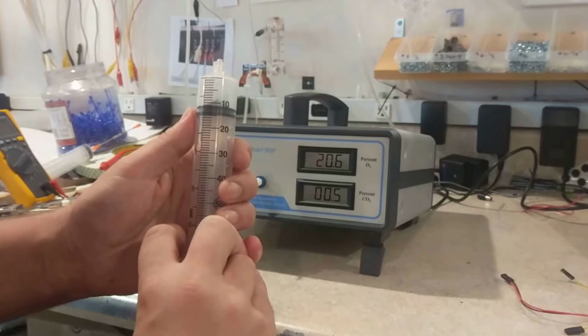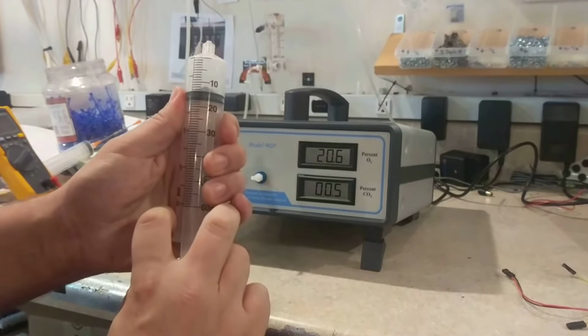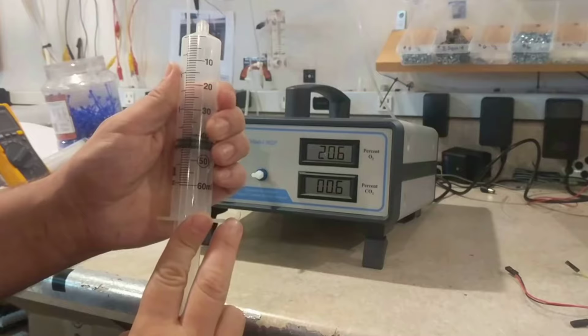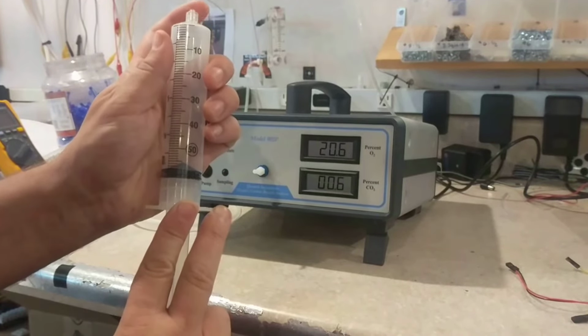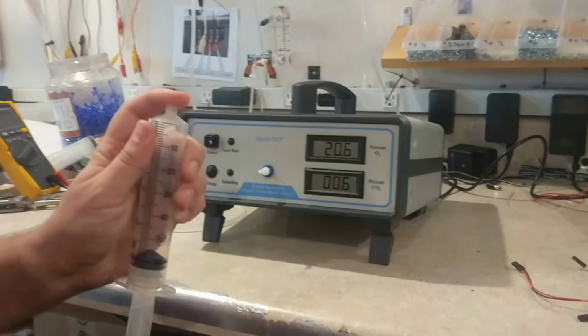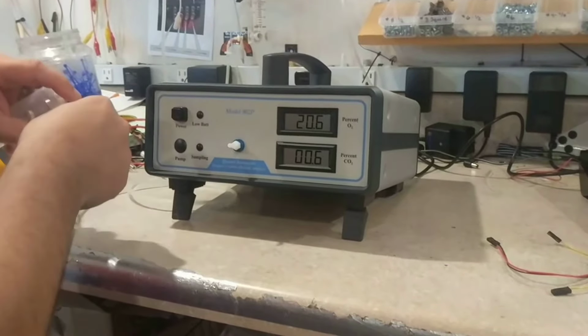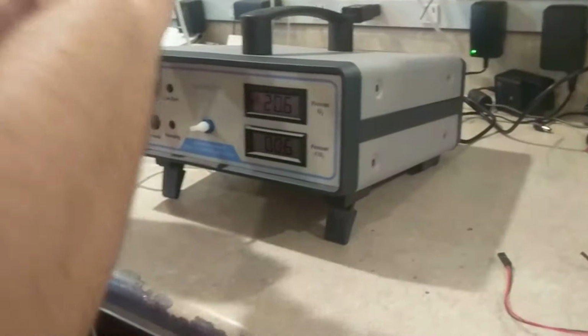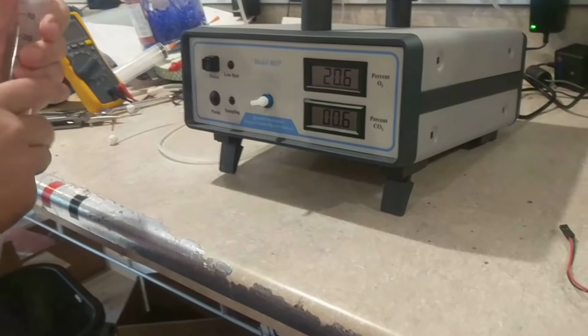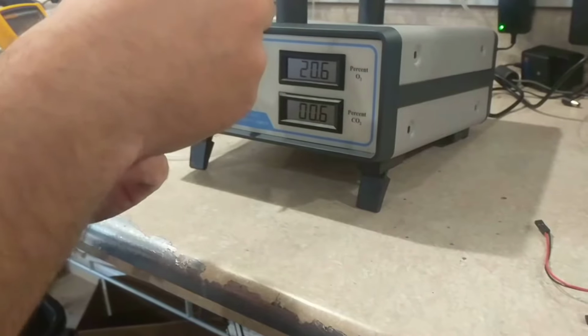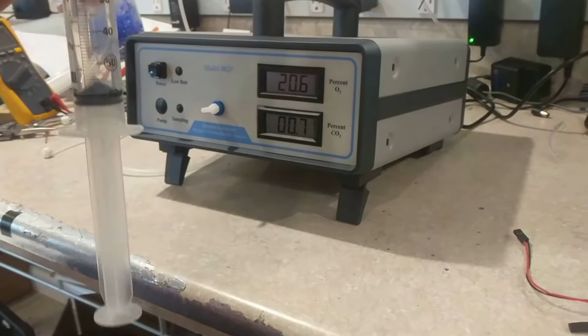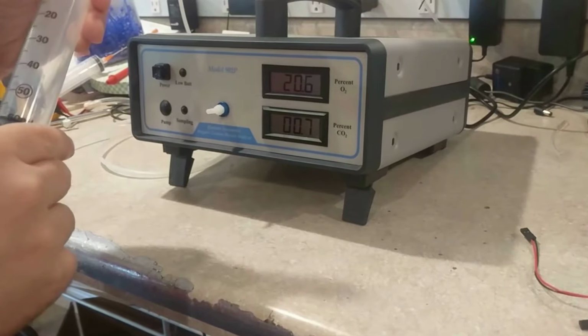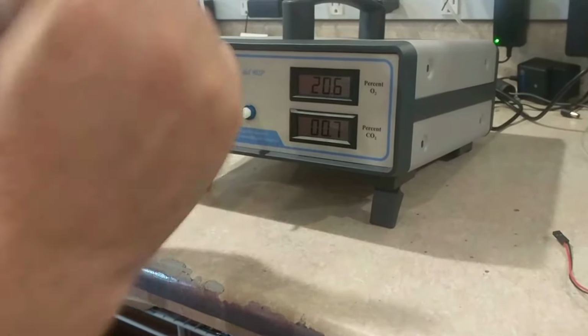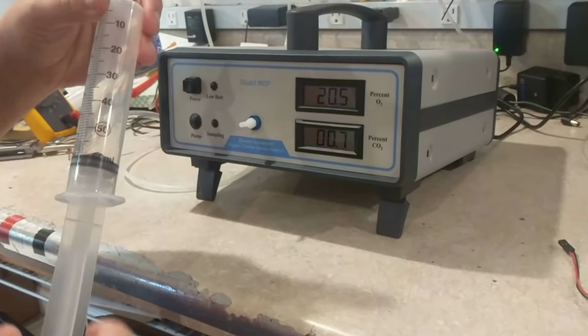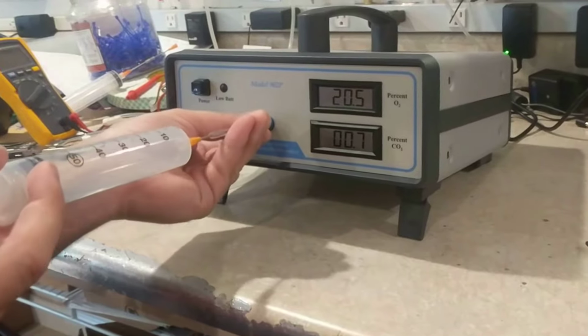And then the next thing I'm going to do is pull in room air. And so the end result of this is that we have 10 cc's of pure CO2. The remainder is ambient air. Ambient air is typically anywhere from 0.04 to 0.10%, so it's not statistically significant. The oxygen is also useful as a marker to show if we've done this correctly, because 5/6 of this should be room air. So now we're going to inject it slowly into the instrument.